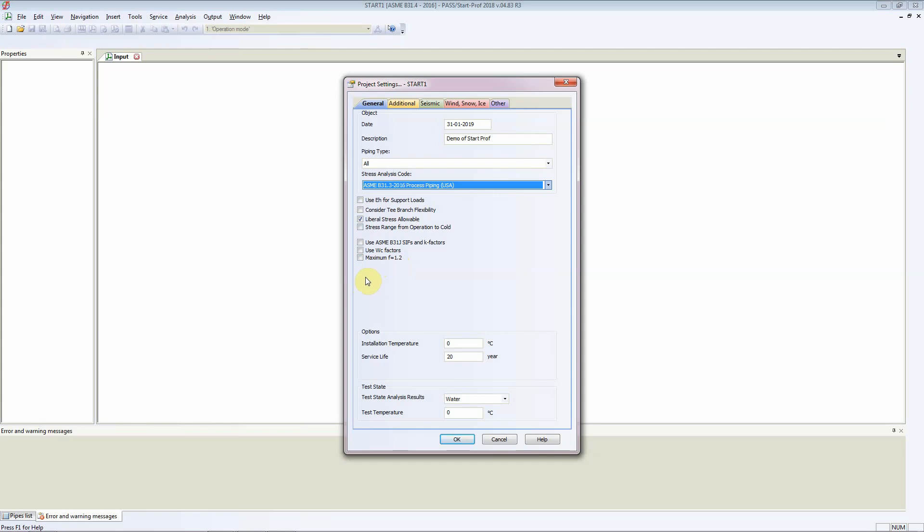The main option that we are concerned about is the installation temperature. For us in this case, the installation temperature is 20 degrees C. The service life of this pipe is 20 years. It will be hydro tested, so the test fluid will be water and test temperature is 20 degrees C.